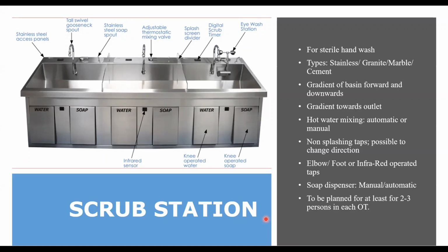and it must be elbow, foot or infrared operated, easier for the scrub personnel to turn the water on and off. And there must be a soap dispenser, either automatically activated or using manual activation. And it must allow 2 to 3 personnel to perform scrubbing at a time.